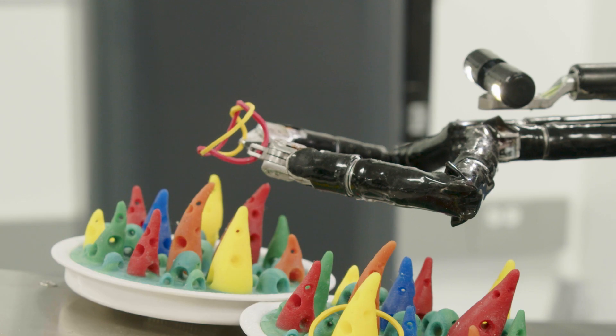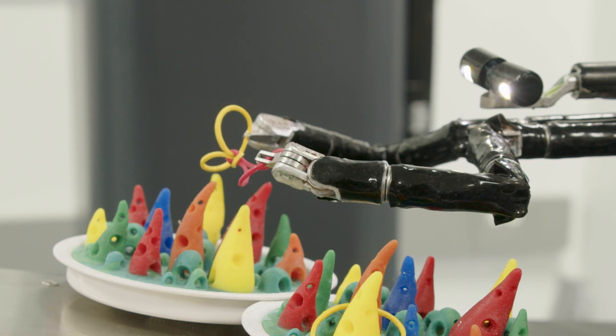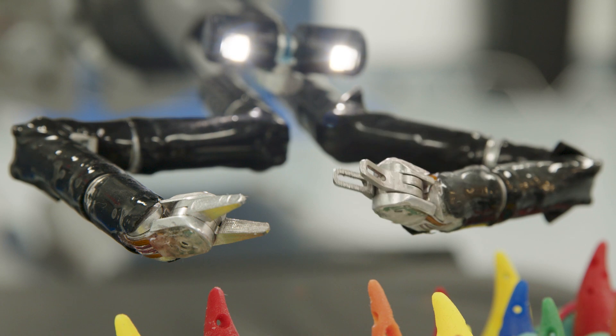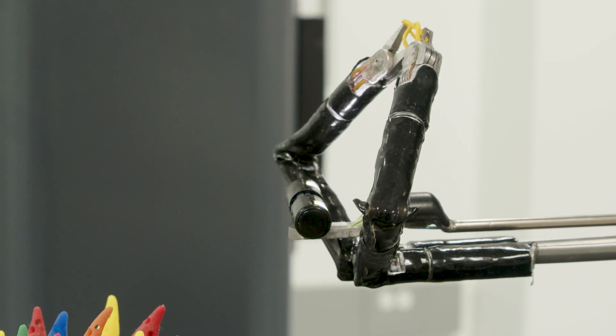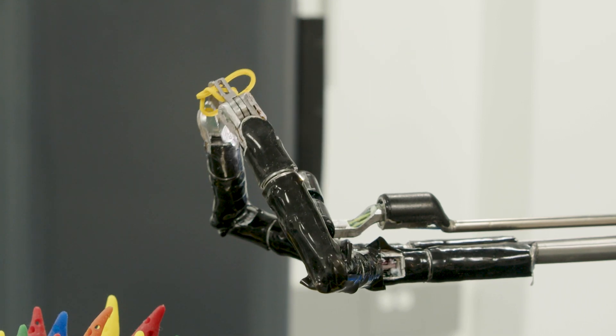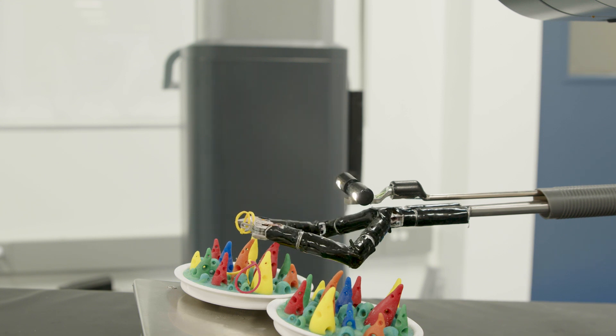The key differentiating technology that we've developed over the years is something we refer to as decoupled actuators. When I move the wrist, I don't want the elbow or the shoulder of the robot to move. I want it to do exactly what I want and only what I want. Doing that actually creates a robot that's easier to control both for the user as well as for the computer itself that's driving the robot. It allows for more degrees of freedom, and you have access to the entire abdomen like no other system out there.